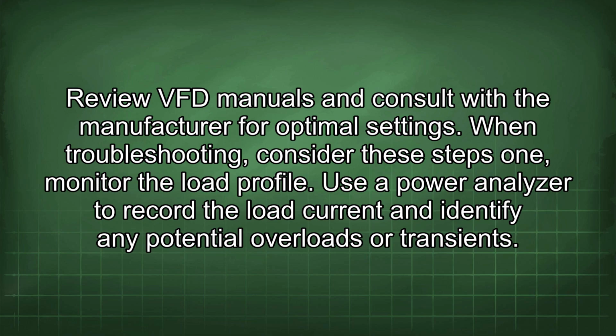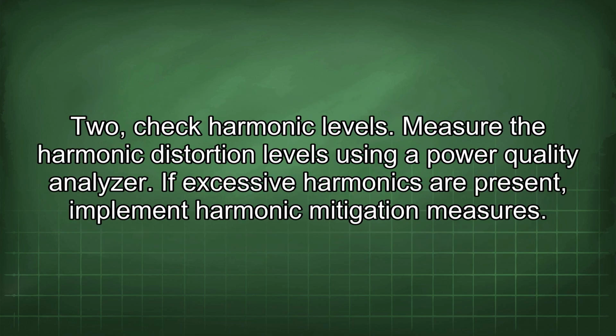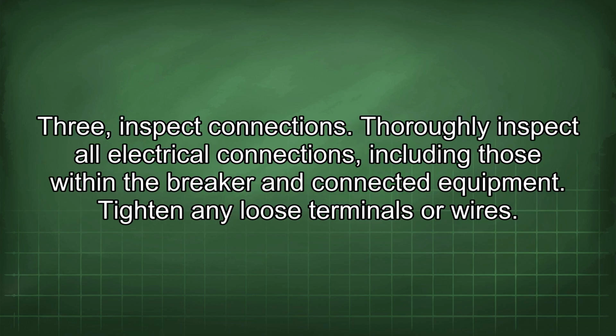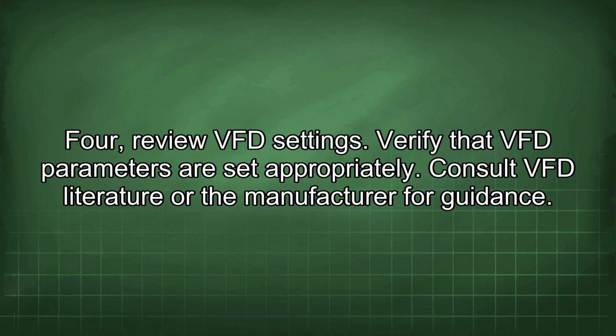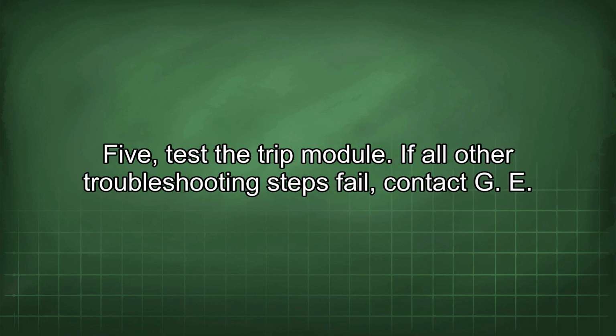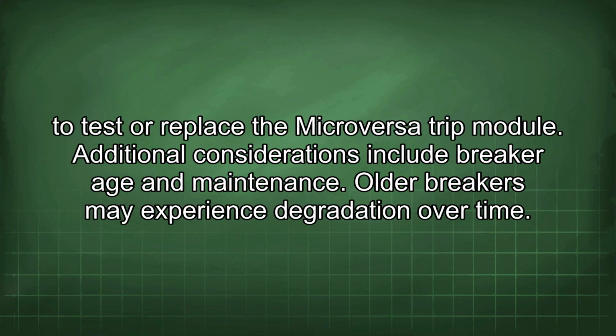When troubleshooting, consider these steps. 1. Monitor the load profile. Use a power analyzer to record the load current and identify any potential overloads or transients. 2. Check harmonic levels. Measure the harmonic distortion levels using a power quality analyzer. If excessive harmonics are present, implement harmonic mitigation measures. 3. Inspect connections. Thoroughly inspect all electrical connections, including those within the breaker and connected equipment. Tighten any loose terminals or wires. 4. Review VFD settings. Verify that VFD parameters are set appropriately. Consult VFD literature or the manufacturer for guidance. 5. Test the trip module. If all other troubleshooting steps fail, contact GE to test or replace the Microversa trip module.